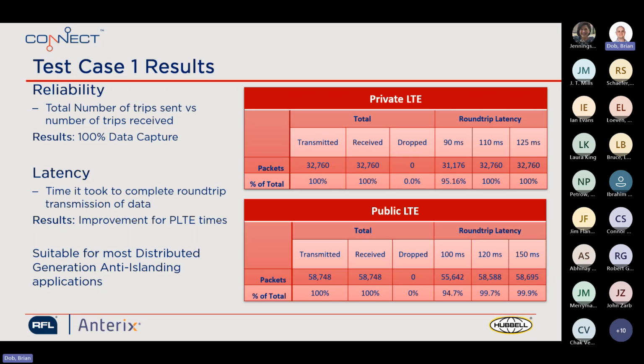So with the public LTE, you can see that we received 99.9% of the trip signals in 150 milliseconds round trip. Whereas on the private LTE, we had 100% within 110 milliseconds. So there's roughly a 40 millisecond difference between the two there. The other thing I would point out too is that in comparison to the public network, the private LTE network is a little bit more consistent. There's less variation in the latency.